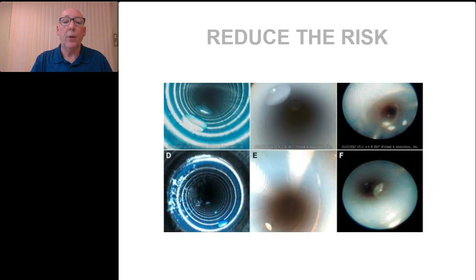So it's all about reducing the risk, making sure that those water droplets that you see in those lumen devices are mitigated, to remove them, evaporate them, so that before they go into steam sterilizers and/or low temperature sterilization, those lumens are in fact dry. So it's all about reducing that risk and making sure that patient safety obviously is even more enhanced with what you're doing.